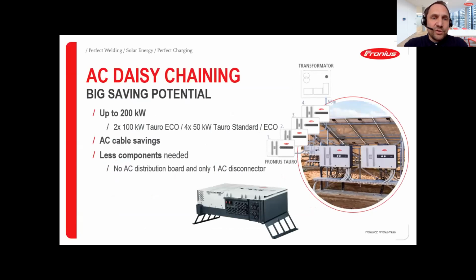So this is what I was talking about, the AC chaining. You can connect up to 4 Tauro inverters, but there's a limit that the total output of these connected inverters must be up to 200 kilowatts. So it's up to you whether it will be 200, 100, or 4 times 50 - it could also be 2 times 50. It's really up to the project. Then, as I said, you will save some cables and need fewer components.